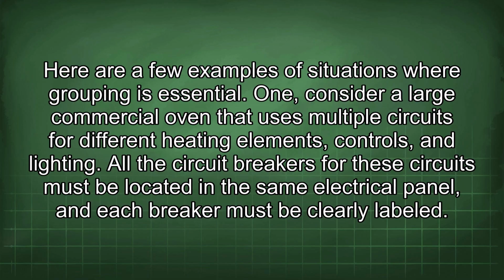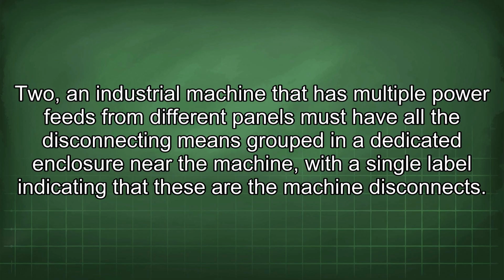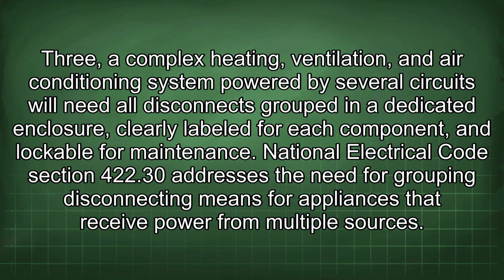clearly labeled. 2. An industrial machine that has multiple power feeds from different panels must have all the disconnecting means grouped in a dedicated enclosure near the machine, with a single label indicating that these are the machine disconnects. 3. A complex heating, ventilation, and air conditioning system powered by several circuits will need all disconnects grouped in a dedicated enclosure, clearly labeled for each component, and lockable for maintenance.